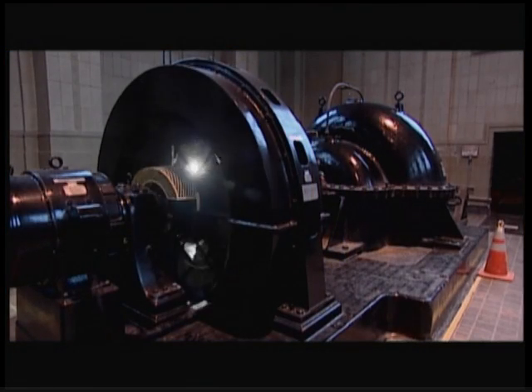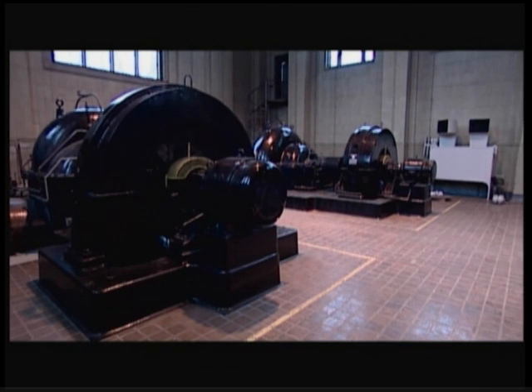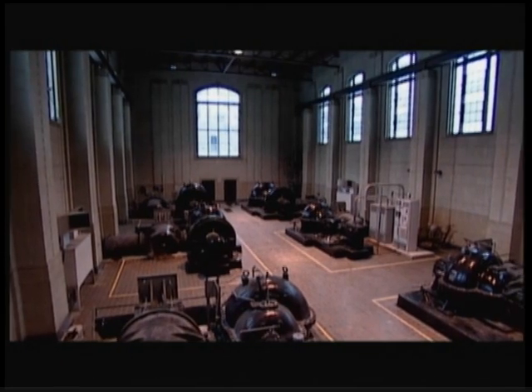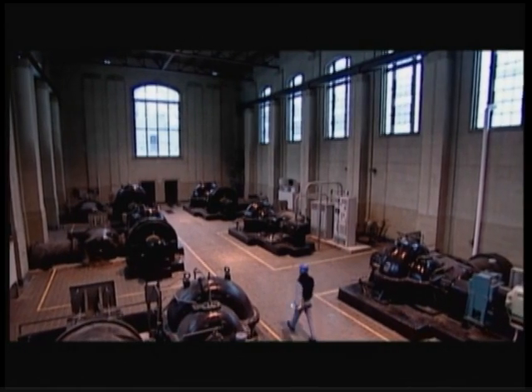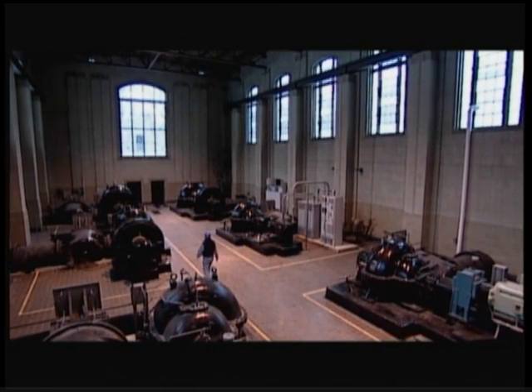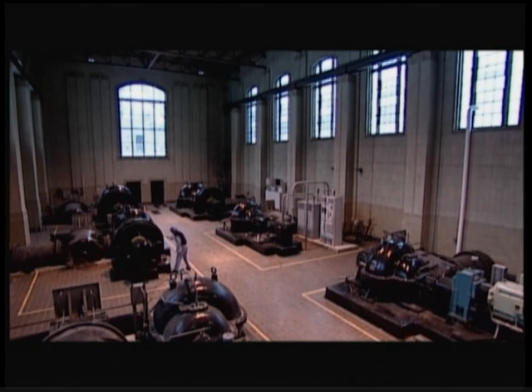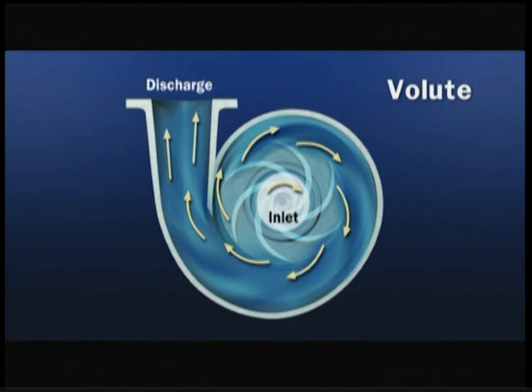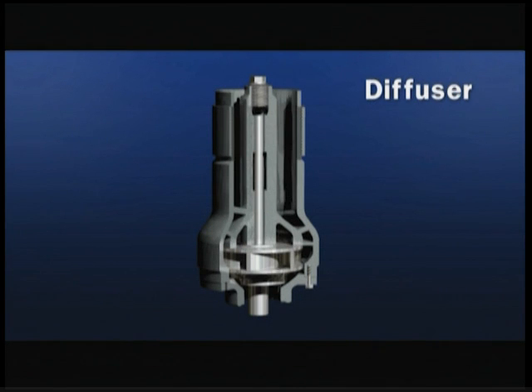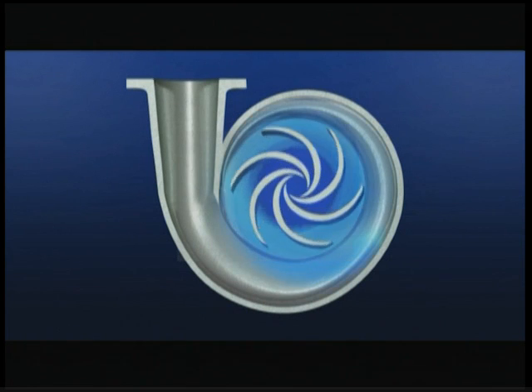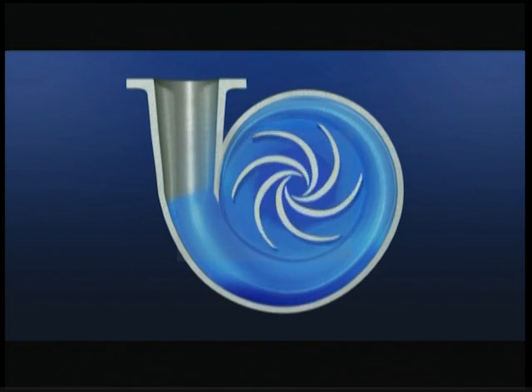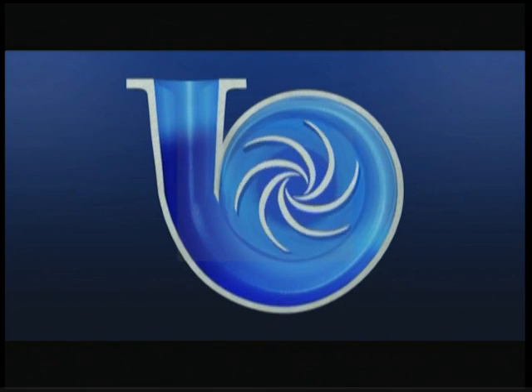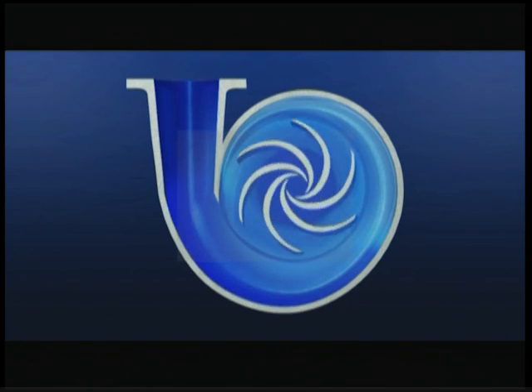Though there are numerous types and manufacturers of centrifugal pumps on the market, most are similar in construction and operation. Velocity pumps use a spinning impeller or propeller to accelerate water to high velocity within the pump casing. This is achieved in one of two different ways: in a volute or expanding spiral casing shape, or through diffuser vanes or channels such as those built into the bowls of vertical turbine pumps. The volute style is also known as radial flow. Water is thrown outward from the center of the impeller into the volute or diffusers that convert the velocity to pressure.